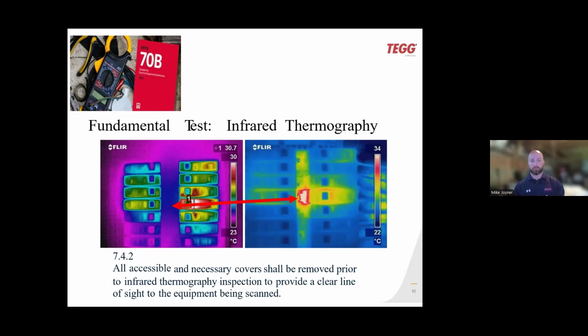When it comes to electrical infrared thermography, you have to open up all the electrical equipment, expose yourself, take the dead fronts off, and be able to see inside. Like the example on the right, that could be a cross-threaded screw, a loose connection - you wouldn't be able to see that if the dead front was on. Infrared scanning does not read through metal, so it's very important to have the right qualified people to take everything off and expose it properly.